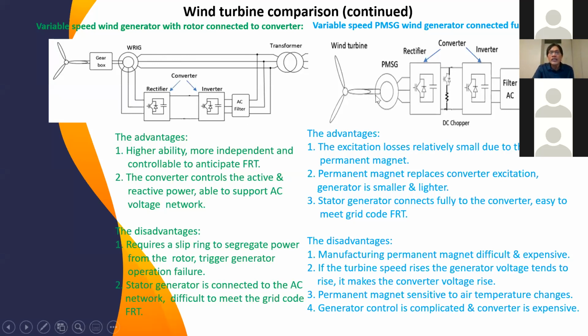The last one is the fully connected turbine. This is the fourth type of turbine. The stator is directly connected to the converter and then connected to the AC network. The advantage here is that, because all the turbine output goes through the converter, with the stator fully connected to the converter, it is easy to meet the grid code. The advantage is mainly because it is fully controlled by the converter. However, the generator control is complicated and the converter is quite expensive because we need a higher rating of converter.